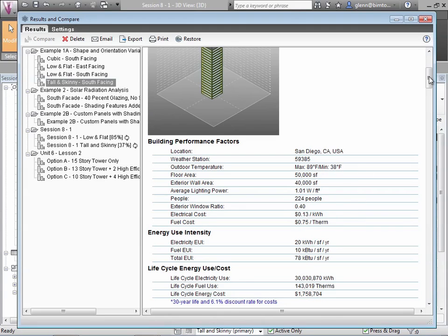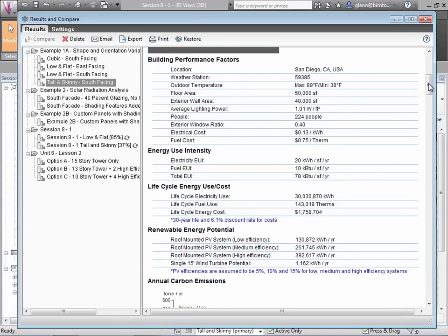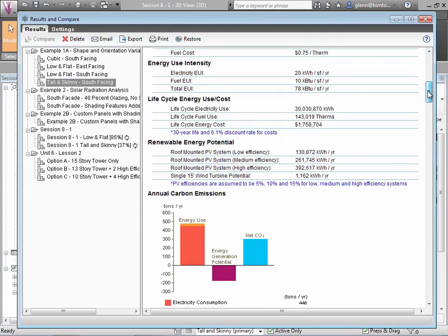It'll give us a figure called the energy use intensity. And the energy use intensity, for lack of any other measure, is a really good way of looking at your buildings. This is how much energy you are using to heat and cool and provide all the loads per square foot. Normalizing everything else, it's just how much per square foot of usable area that you're creating are you using. That's a pretty good measure. At a high level, we could talk about our buildings just in terms of our EUIs and compare them at that level and get some sense of where it is.